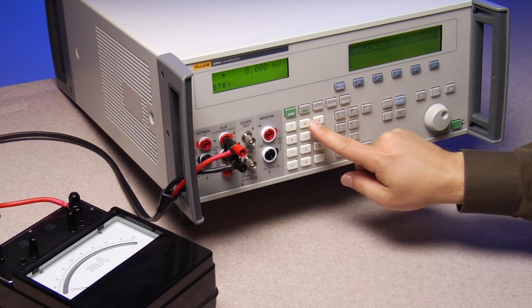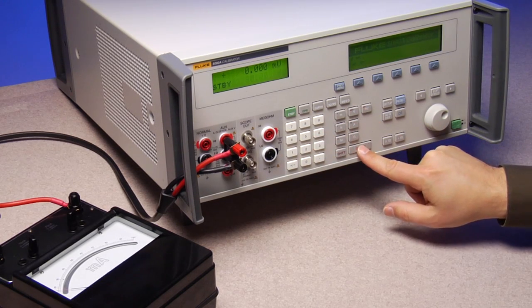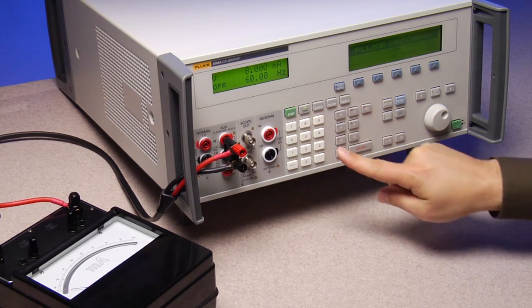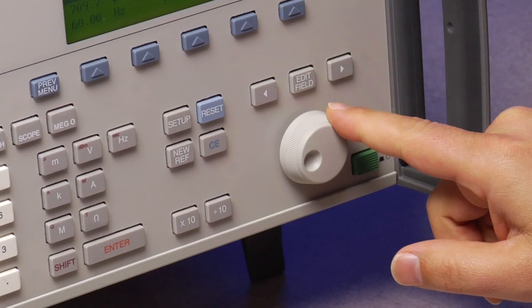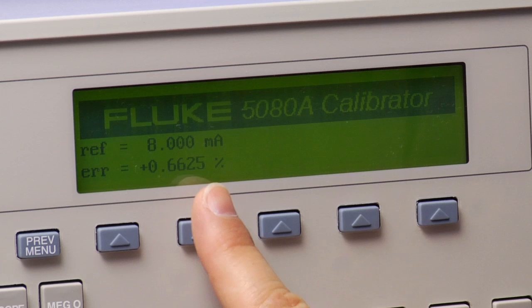This 5080A calibrator is set up to calibrate an analog amp meter. For each test point we can slew the source output until the meter reads nominal value. From the front panel turn the knob or use the keypad. This can also be achieved with 5080 cal software. We'll record the nominal reading of the analog meter and the output of the calibrator and calculate the error. Or you can read the error directly from the 5080's front panel display.